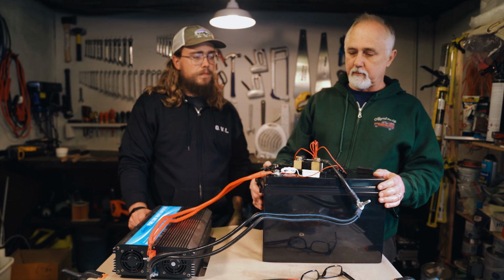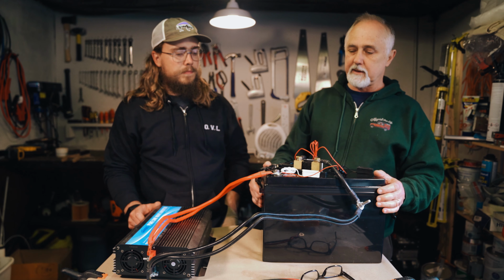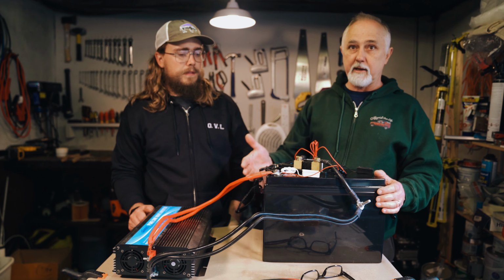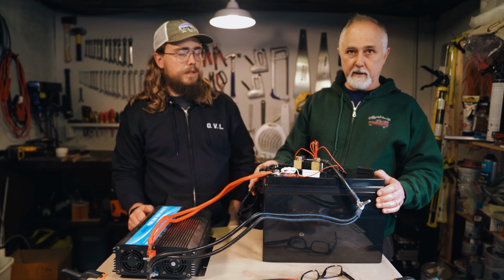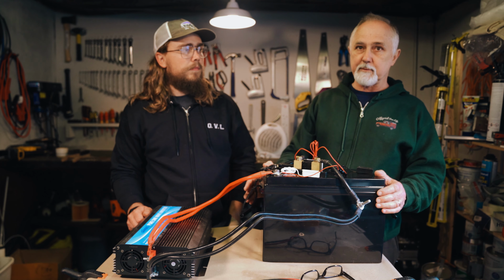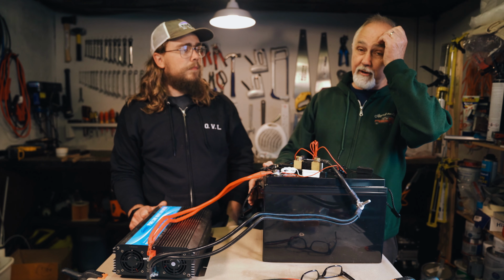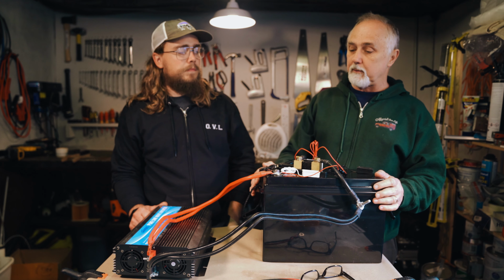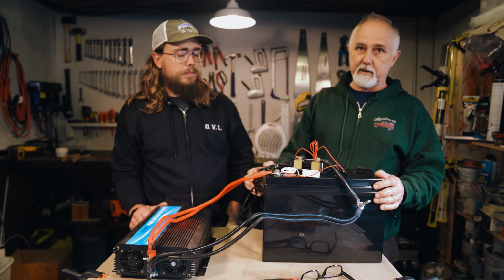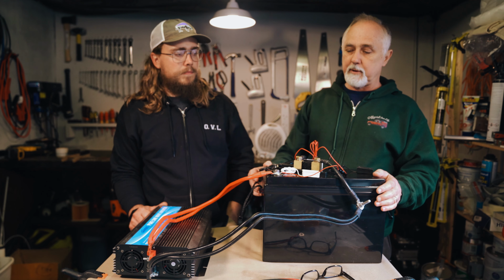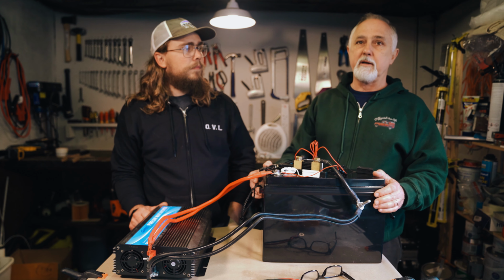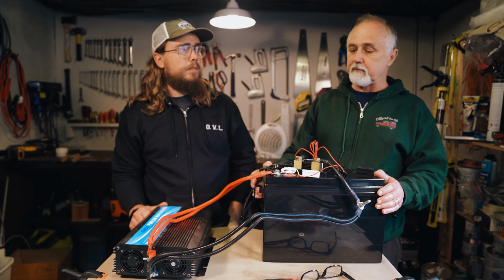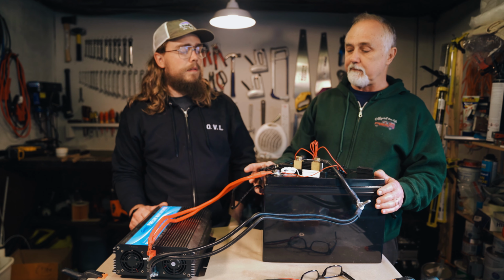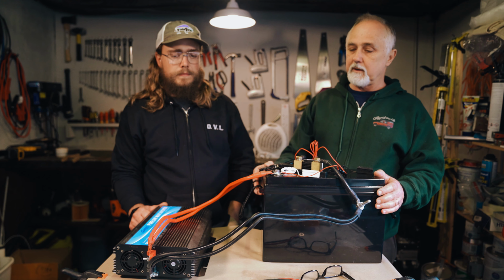So it's a standard drop-in replacement battery size with a 150 amp BMS, rated at 150. We ran 160 to 170 amps for a lot of the time on that 150 amp BMS. Well pleased with Dali - when they say the BMS is 150, they mean it is 150 plus, not maybe up to 150. It is definitely 150 or more.